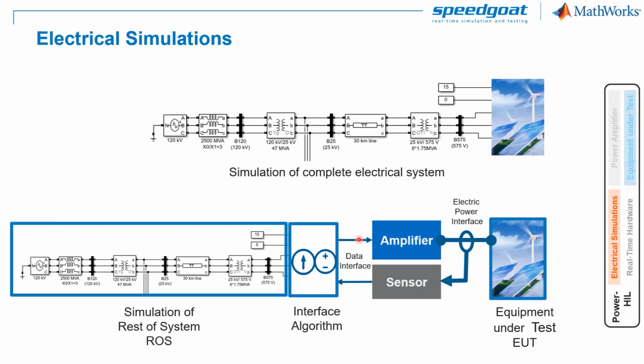In such a test setup with two electrical systems, the grid simulation on the left and the inverter on the right, signals also must be exchanged in the opposite direction. Therefore, a sensor signal is typically used that closes the loop. Here, an interface algorithm converts the three-phase electrical connections from the grid simulation into bidirectional signals.